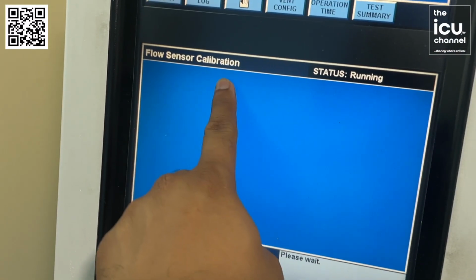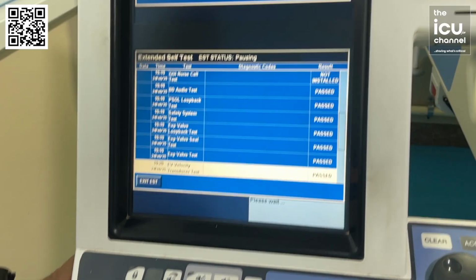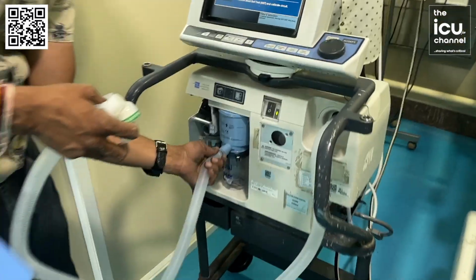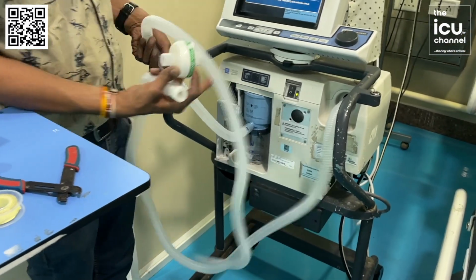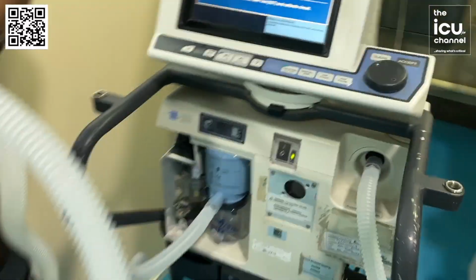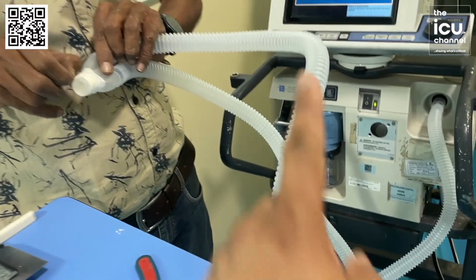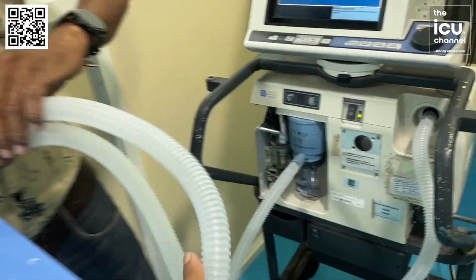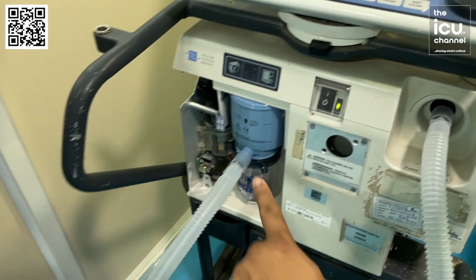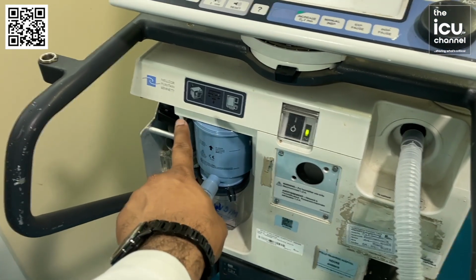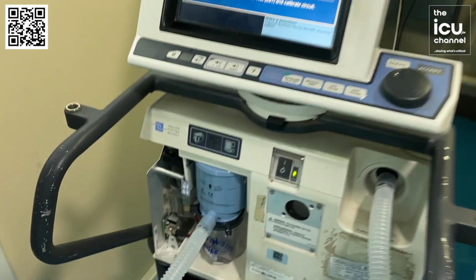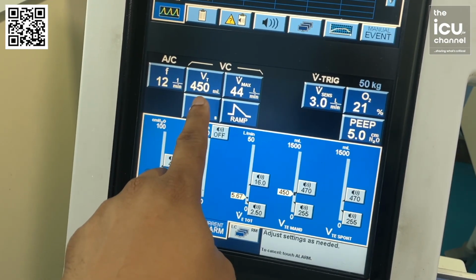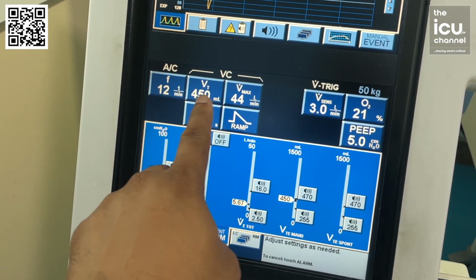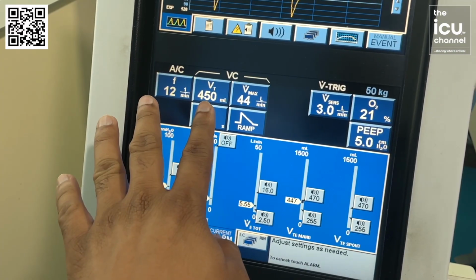Flow sensor calibration. Latest loading. So all tests have been passed. So we are connecting a dummy circuit to the ventilator. This is the inspiratory limb. Air goes from the inspiratory limb to the patient, and from the expiratory limb, it goes back to the filter and then to the expiratory flow valve and the safety valve check. So we have set the tidal volume of 450.